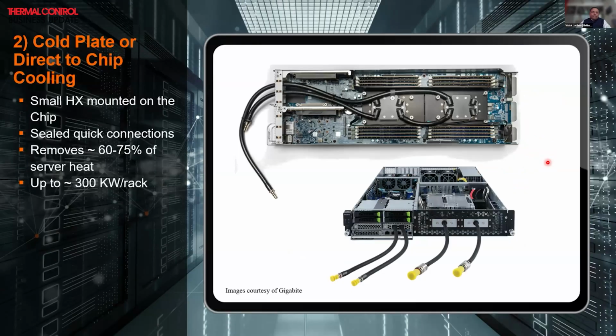Coming to the second type, which is cold plate or direct to chip cooling, this is where the plates are installed on the circuit boards, and chilled water is supplied and circulated on these plates in order to keep the semiconductor inside cold. This has a capacity of up to 300 kilowatt per rack, and this removes up to 60 to 75% of the heat from the semiconductor from the rack.